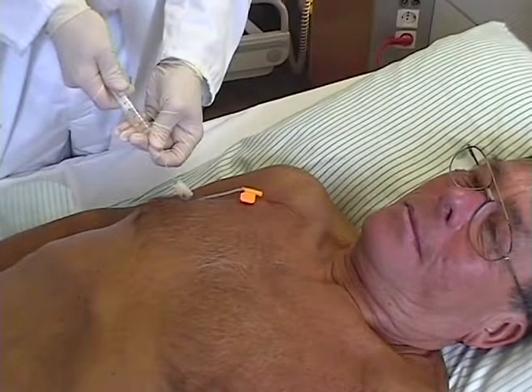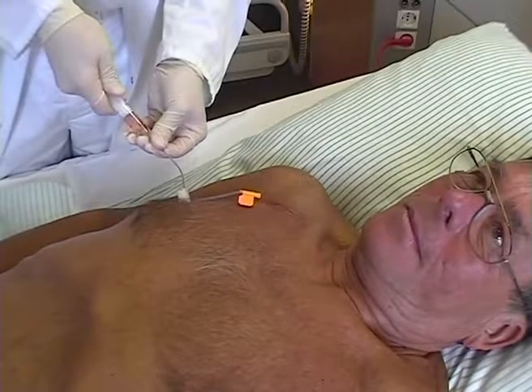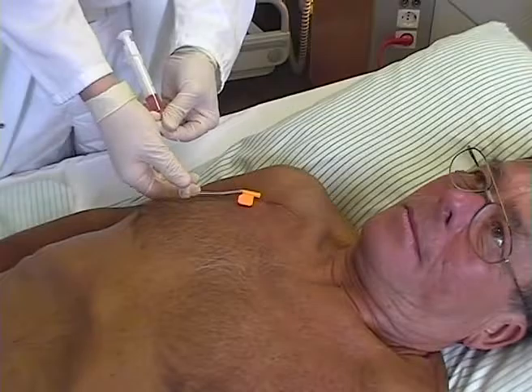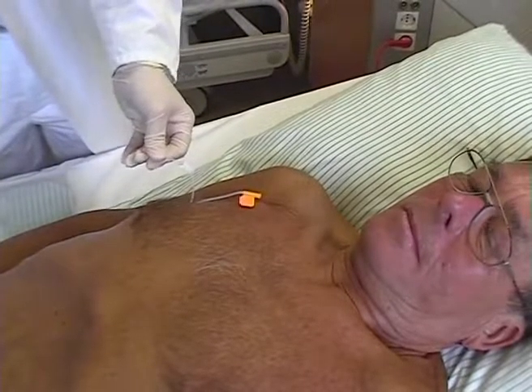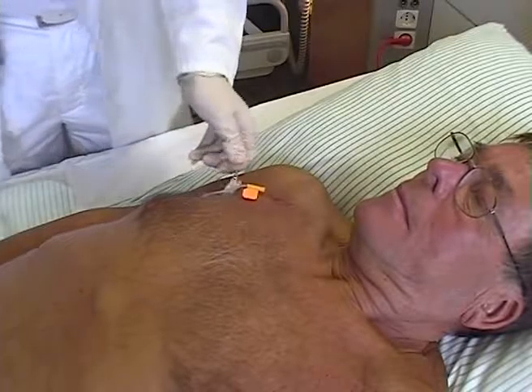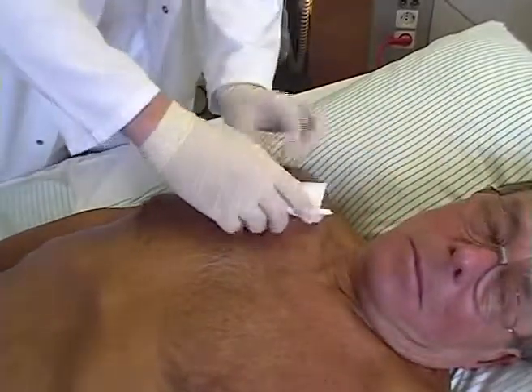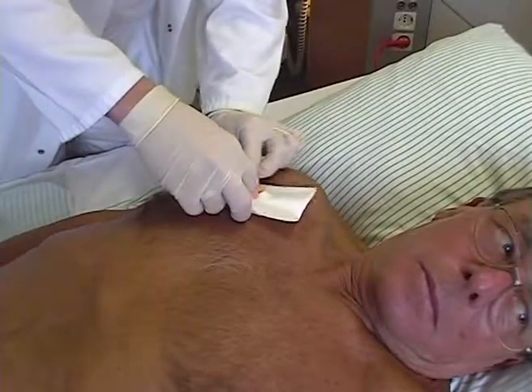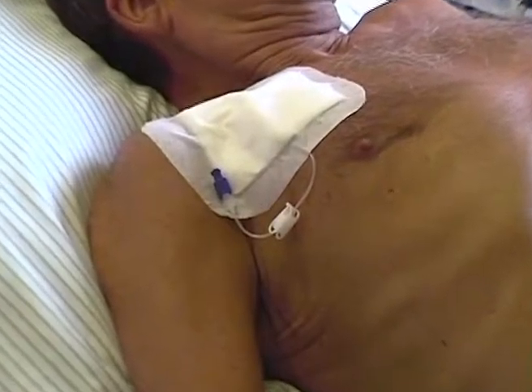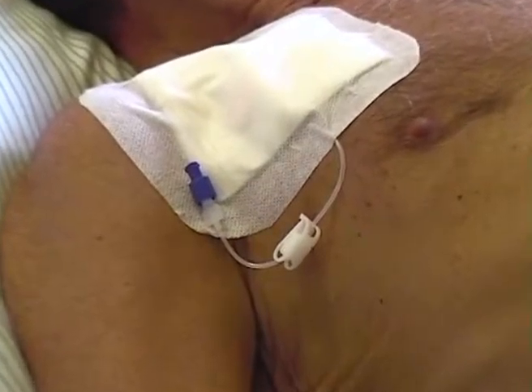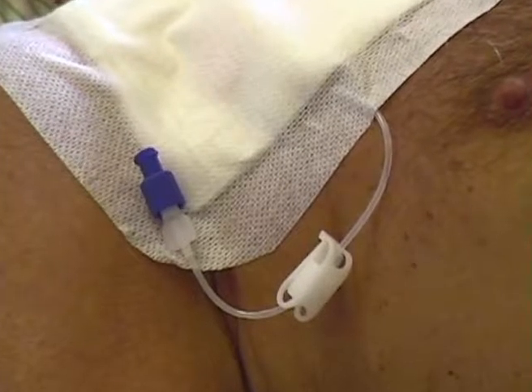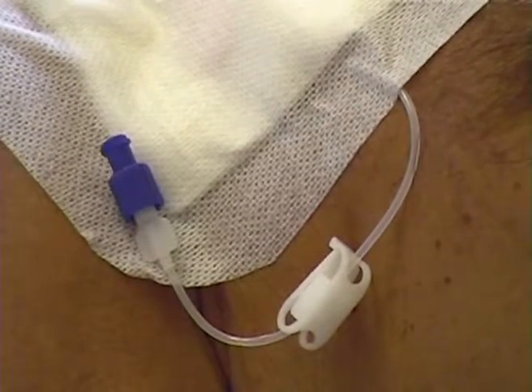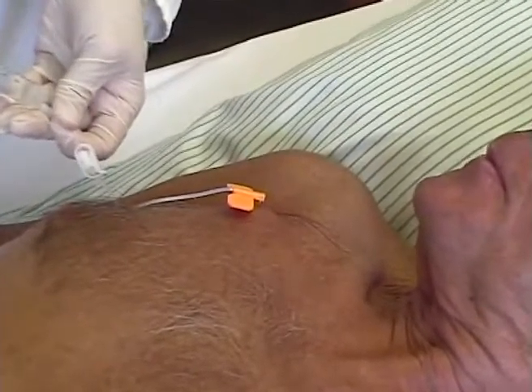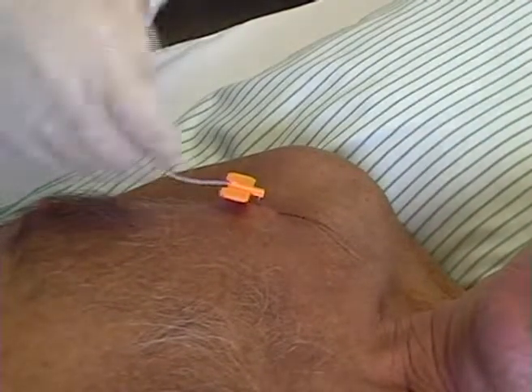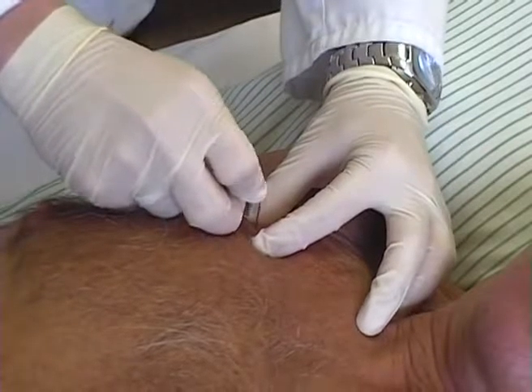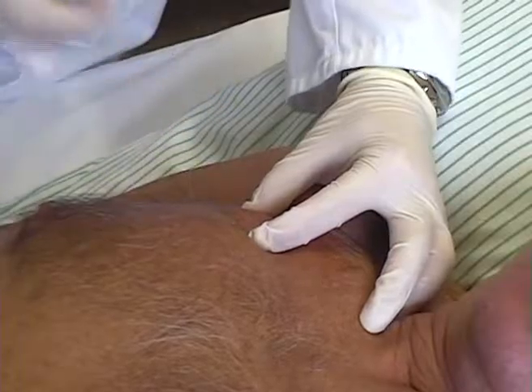The system must be filled with heparinized saline after each use and after longer periods of non-use. 1,000 international units of heparin in 10 ml of 0.9% saline is recommended. In the literature, however, evidence of the advantages of heparinization has not been conclusive. Of paramount importance is thorough flushing of the system with saline to eliminate stagnant substances. Remove the needle only when the check valve is closed to prevent blood flow into the system or motion of the membrane. For drawing blood, a 20-gauge needle should be used.